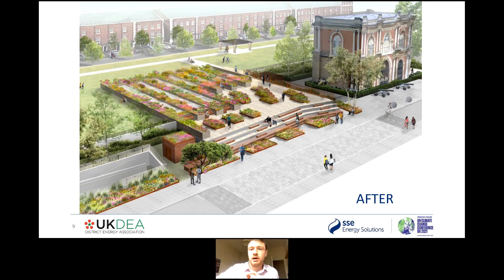So just to summarise with a couple of conclusions - I won't read these in depth, I'll leave them up for everyone to peruse. But the key guidance for air source heat pump system design we'd propose, as a result of this modelling, is that the impact of these issues shouldn't be overlooked, and consideration of air recirculation should be integral to the outline design and any feasibility studies, specifically regarding location of the heat pumps and air-cooled heat exchangers. So our key conclusion would be: can space be made on a rooftop?